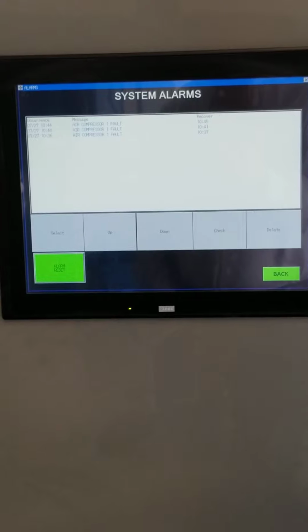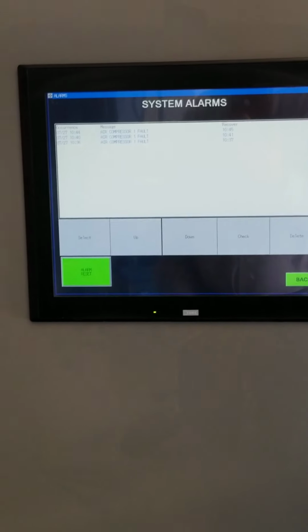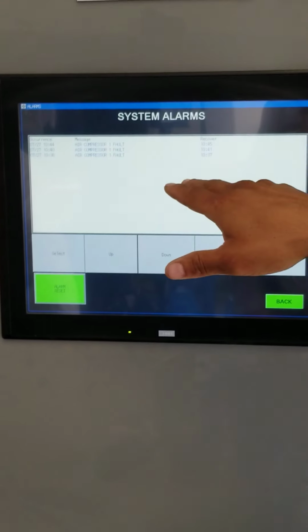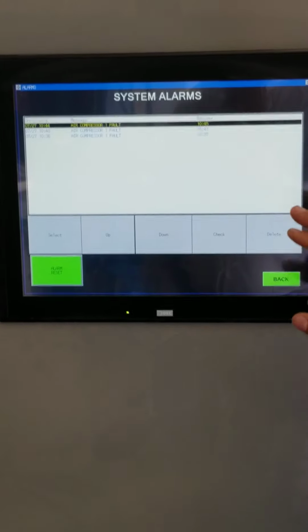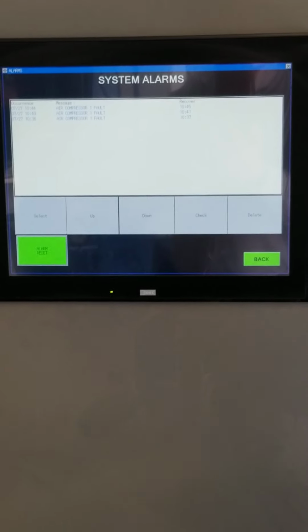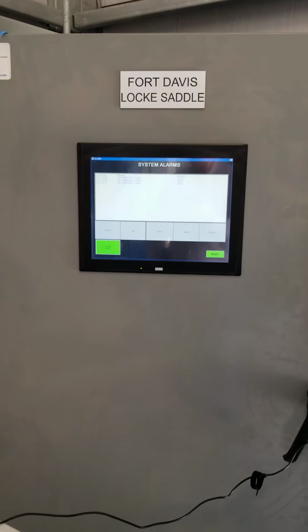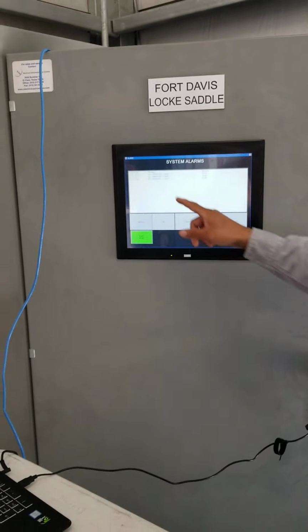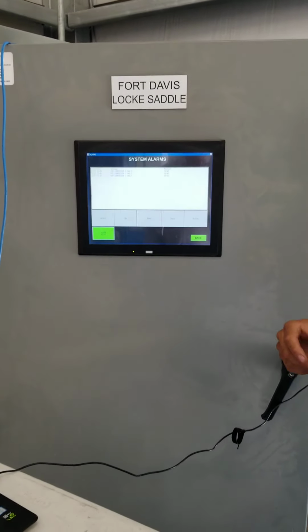Air compressor 1 fault, which will be that compressor over there. But it will tell you the time, the date, and it will store it in there unless you go in there and select it, and you can erase it. But if not, you can leave it alone. Blue means that it's been acknowledged. Red means it's active. So if you see highlighted red, it means that the problem still exists.